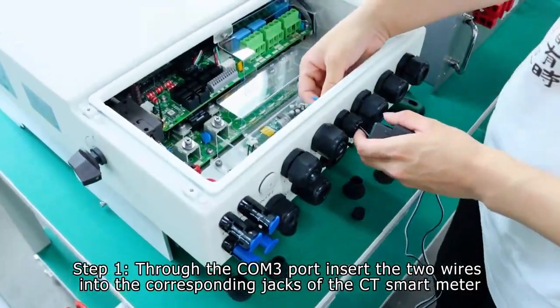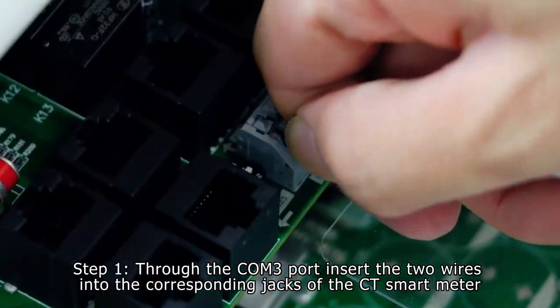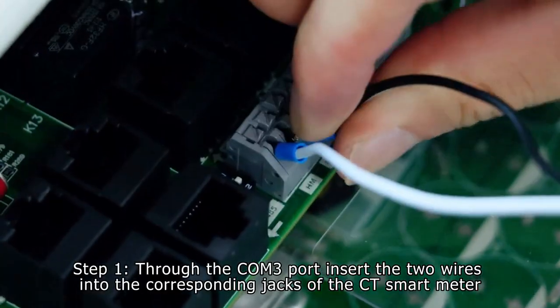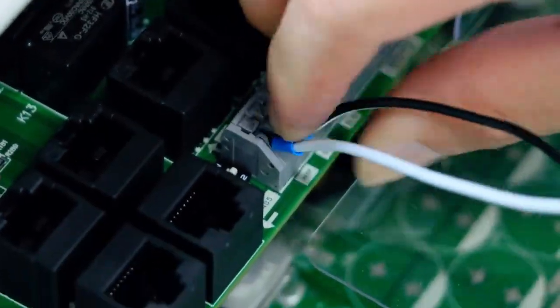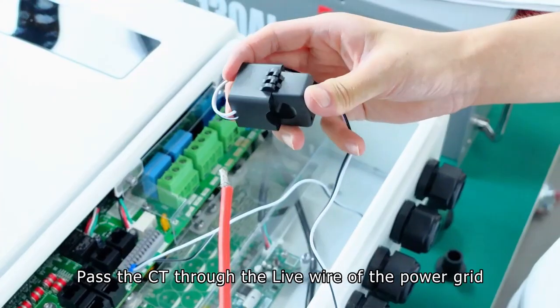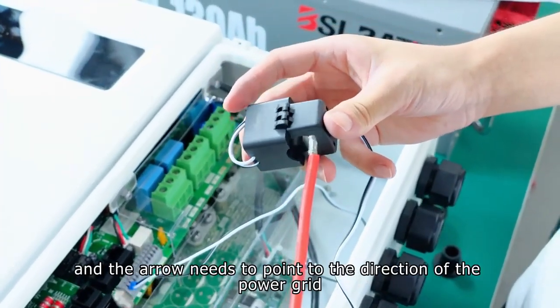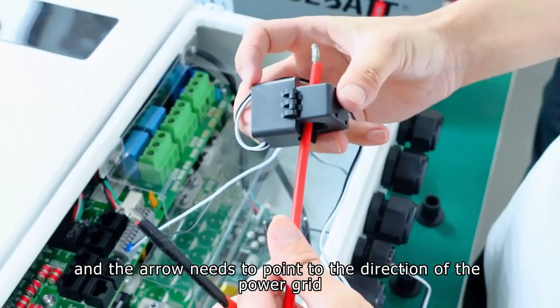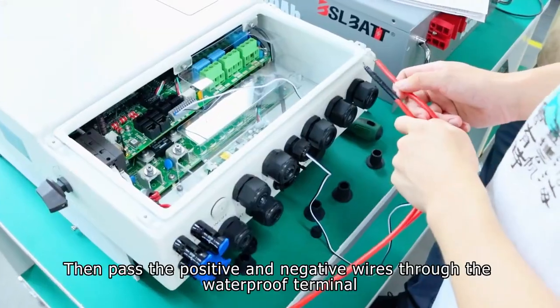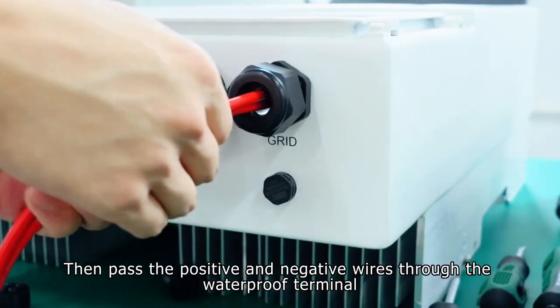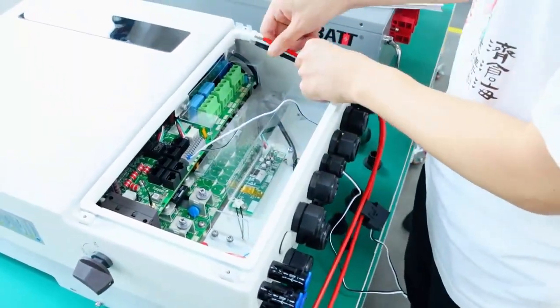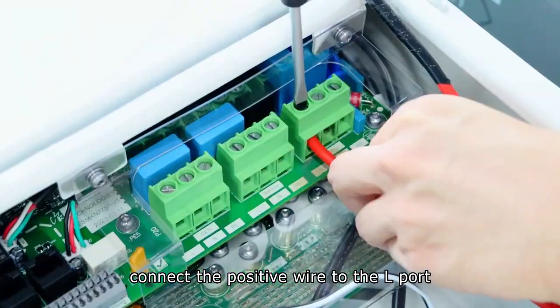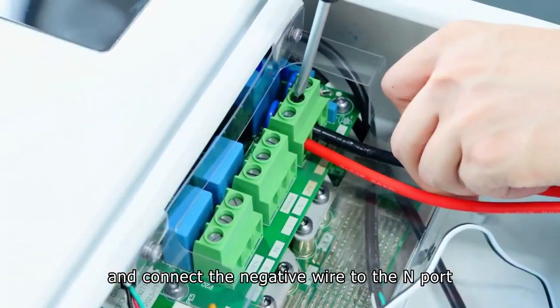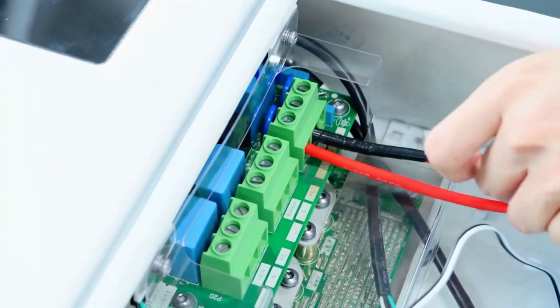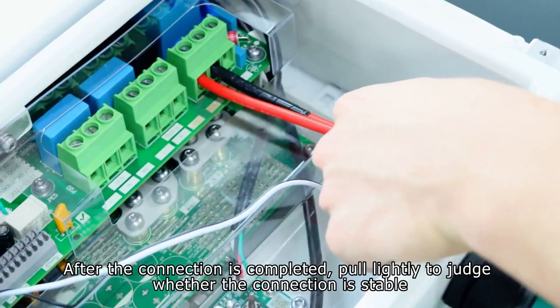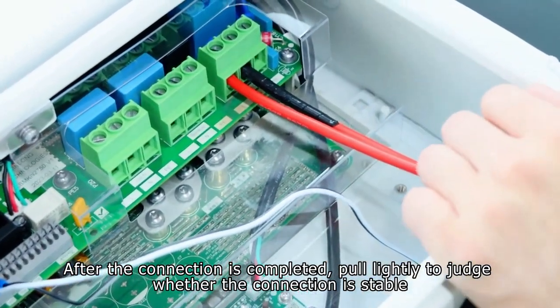Step 1. Through the COM3 port, insert the two wires into the corresponding jacks of the CT smart meter. Pass the CT through the live wire of the power grid, and the arrow needs to point to the direction of the power grid. Then pass the positive and negative wires through the waterproof terminal. Connect the positive wire to the L port, and connect the negative wire to the N port. After the connection is completed, pull lightly to judge whether the connection is stable.